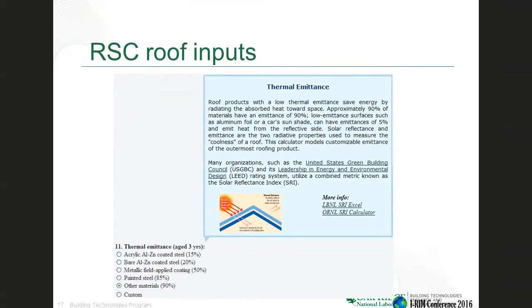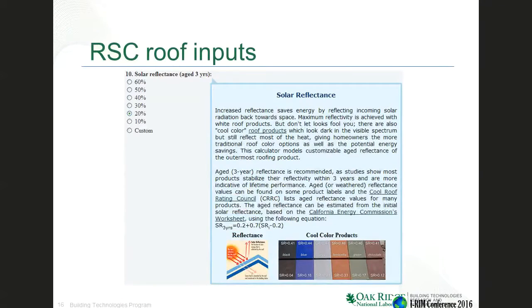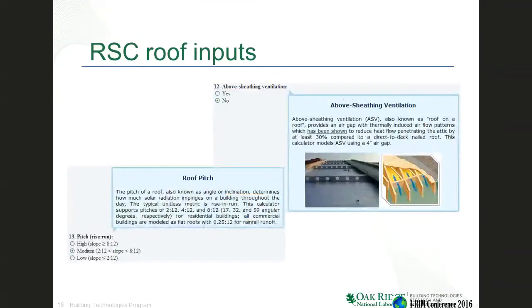The outside roof layer not only has a reflectance — how much of the sun gets reflected — but also a thermal emittance. As it heats up, it emits long wave radiation. Over 90% of materials have an emittance of 90%. But if you have a metal roof or a special type of coated roof, you can get a lower emittance, which is actually a little more energy efficient. These questions are always ordered from least energy efficient at the bottom to most energy efficient at the top, so you can generally find out what the more energy efficient option is for each question.